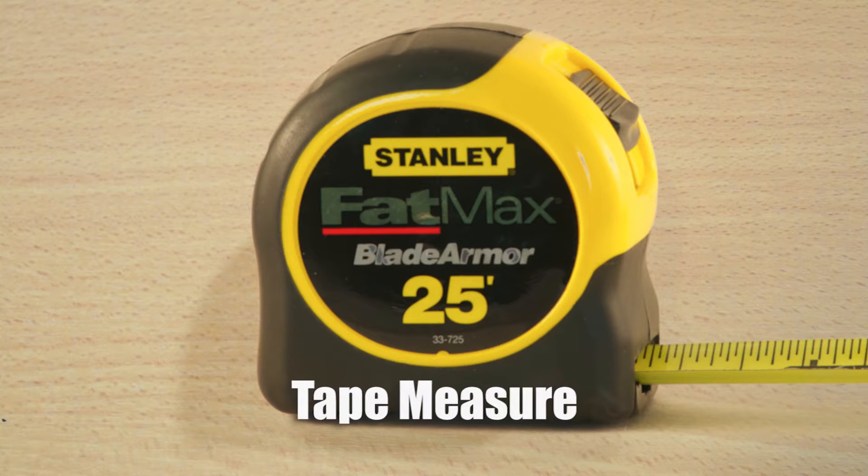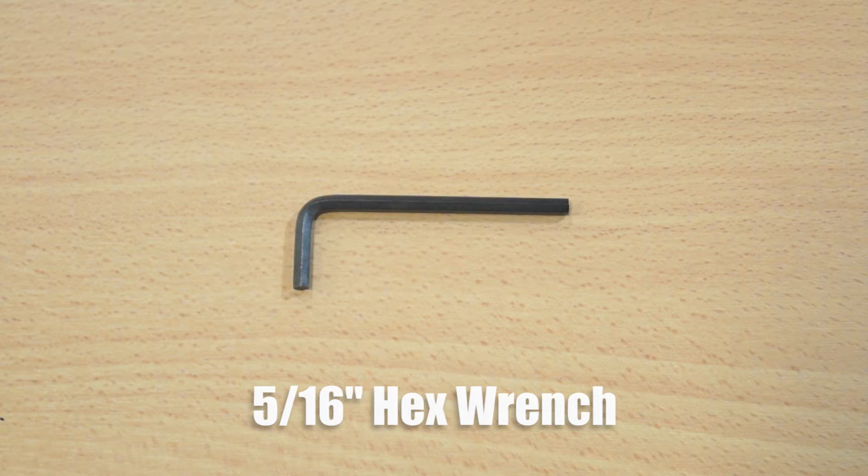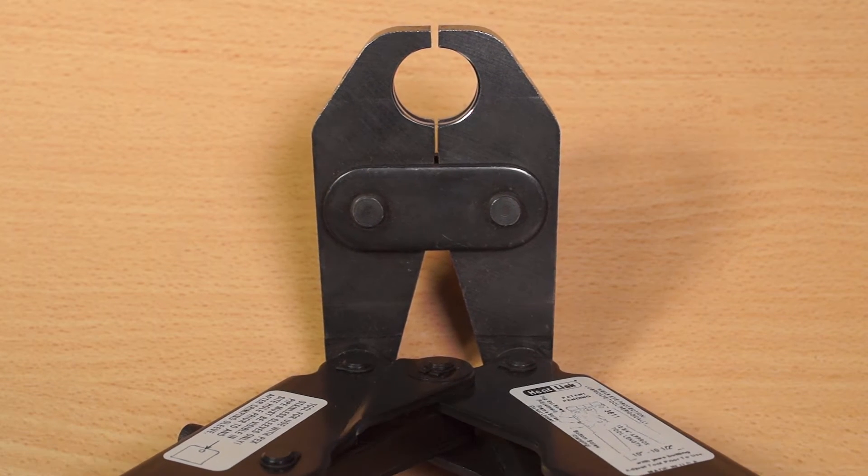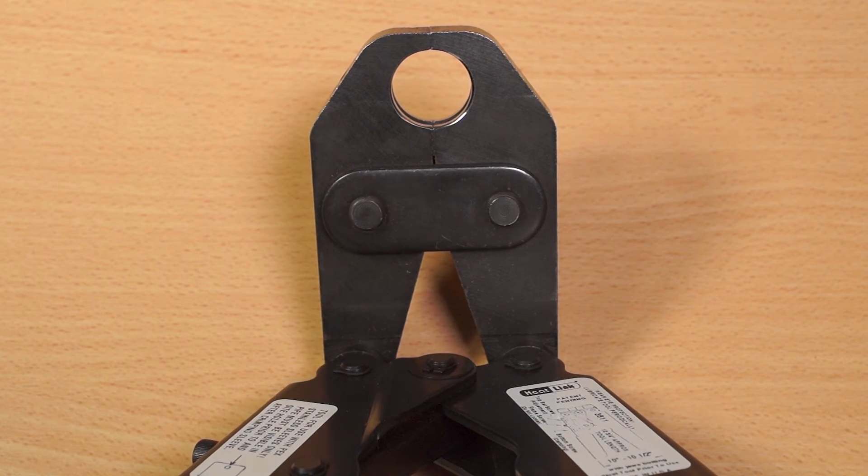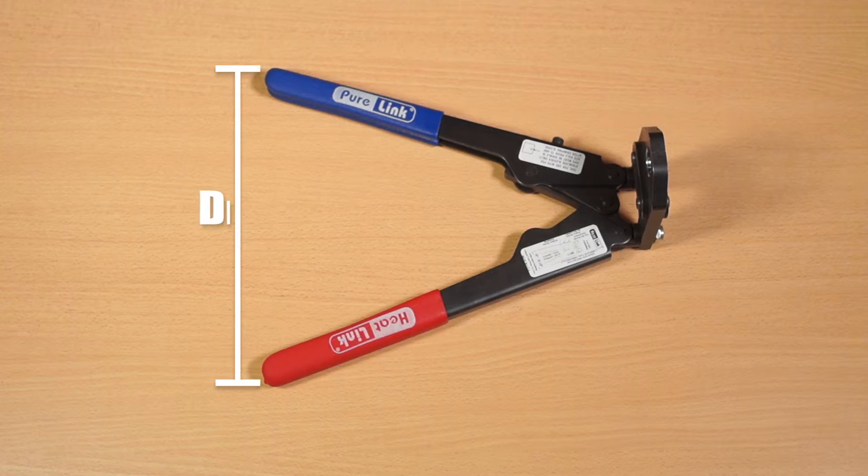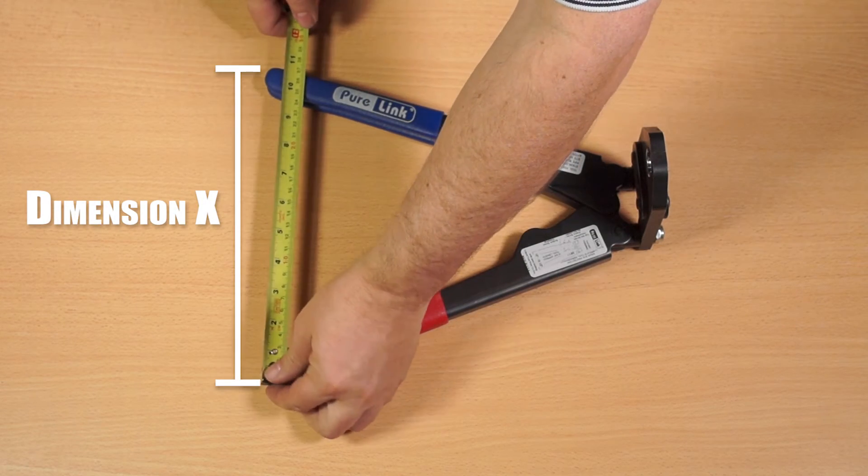You will need a tape measure, the go no-go gauge, and a 5/16 hex wrench. Close the handles until they reach the preload position, just as the jaws butt together. Measure dimension x from the outside edges of the handles and compare to the measurement in the potable installation guide or on the tool's adjustment sticker.